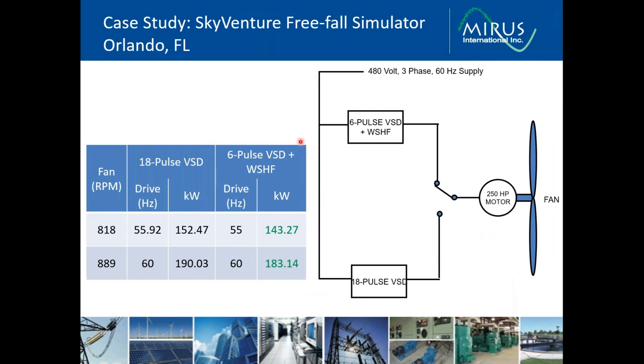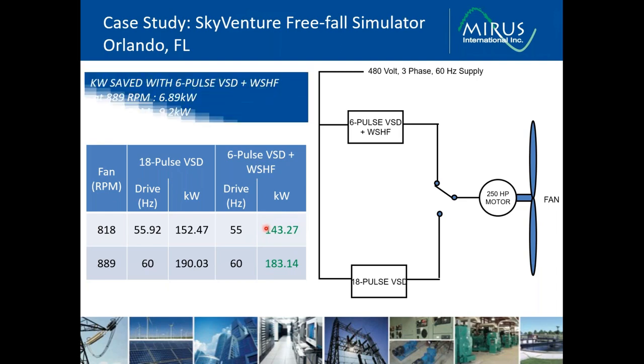When they switched to the 6 pulse drive with the wide spectrum filter, at the higher fan speed, the power consumption dropped substantially to 183 kilowatts. So this is real power, a real power reduction. But even more interesting is that under the lighter or slower fan speed, the drive actually operated at an even lower speed because the passive filter improved the operation of the drive system. So they got 818 RPM with only 55 hertz driven by the drive. That reduced the power consumption even further to 143 kilowatts.